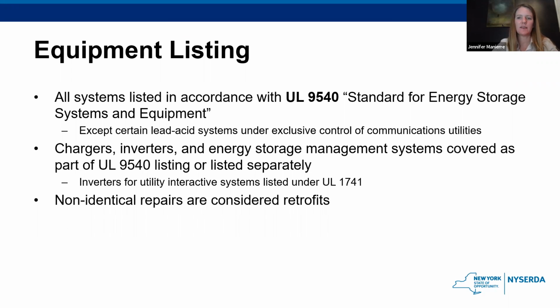Okay, and if we remember back to that circle diagram where we started with cell quality, not just cell quality but all of the equipment, the code requires it to be listed and meet certain specifications. For example, UL 9540 is the standard for energy storage systems and equipment. There's an exception for certain lead acid systems, but generally speaking, all of these need to have the UL 9540 certification. The chargers, inverters, and the energy storage management system might be included in that UL 9540 listing, or they might be listed separately under separate UL numbers. And anytime you're changing a system after the fact, if you're not doing a perfectly identical repair, it's basically going to be treated as if you were applying to build a new system, a retrofit. And it would trigger all the code requirements all over again.